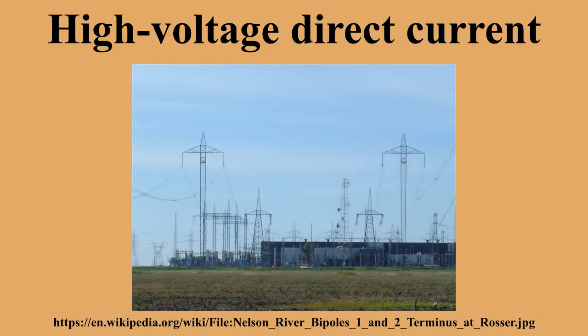This capacitance is in a parallel circuit with the load, where alternating current is used for cable transmission. Additional current must flow in the cable to charge this cable capacitance. This extra current flow causes added energy loss via dissipation of heat in the conductors of the cable, raising its temperature. Additional energy losses also occur as a result of dielectric losses in the cable insulation.